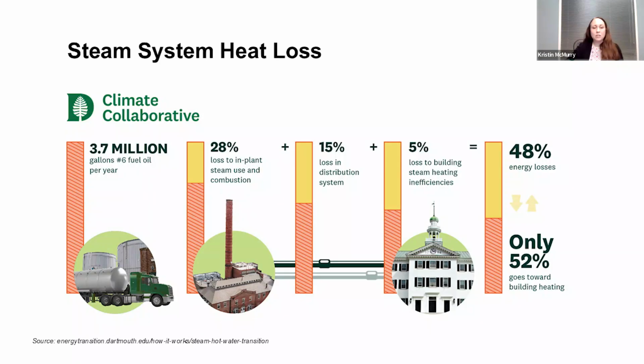Yeah, so there are some losses that are just inherent to a steam system. You're going to lose about 20% just because you're doing combustion, which is going to be the case whether you do steam or hot water. And then for steam, there's another 8 to 10% that you're going to lose to in-plant steam use. And then you're going to lose some heat in the distribution system because you're distributing it at a very high temperature, a lot higher than the ground.